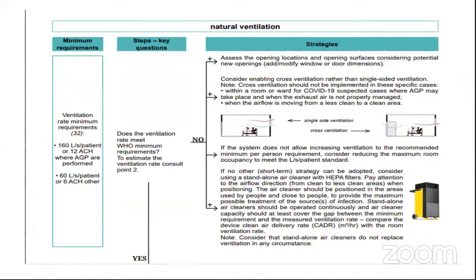What are the openings? We need to ensure that there is cross ventilation, especially in the room or ward where COVID patients are and where the aerosol generating procedure is also taking place. We need to see that the airflow is from less clean to a cleaner area. We need to check on the occupancy. If the ventilation system is not providing the fresh air intake to that standard, we really need to reduce the occupancy of that particular room per liter per second per patient standard.